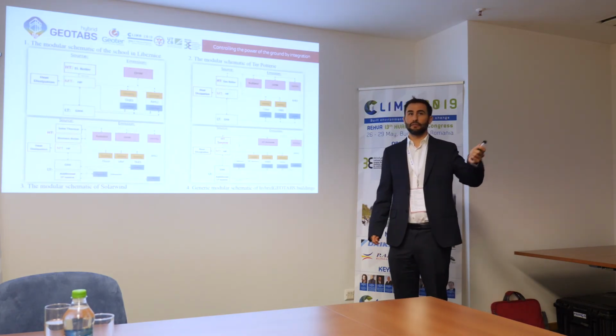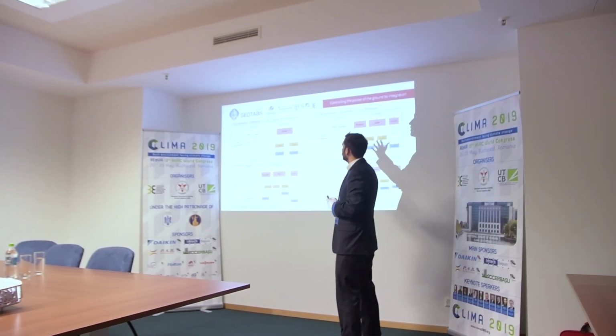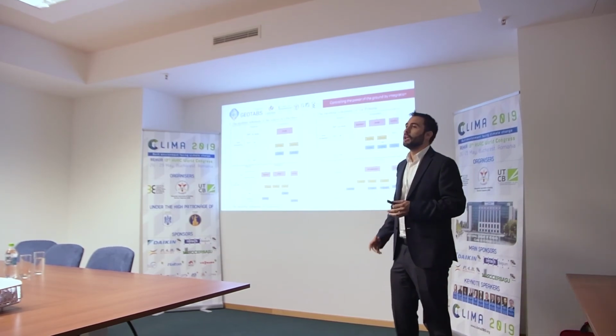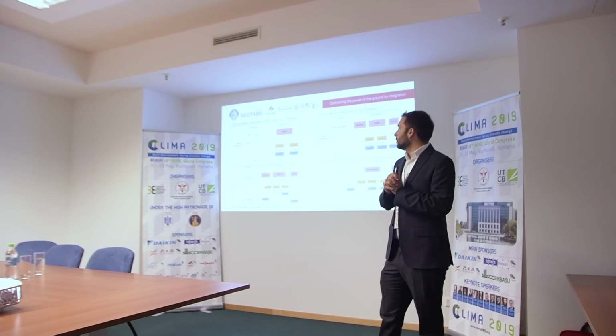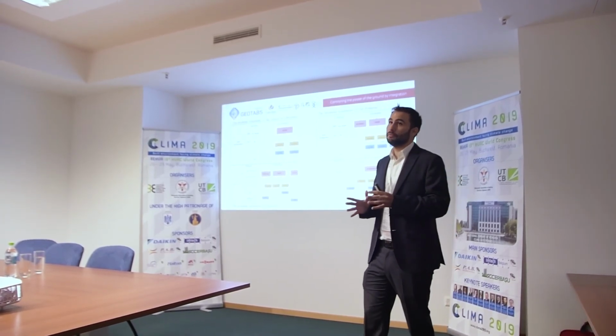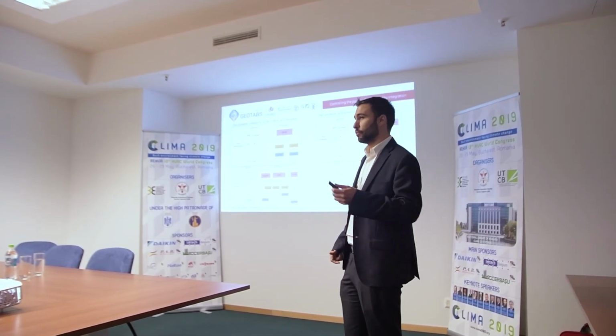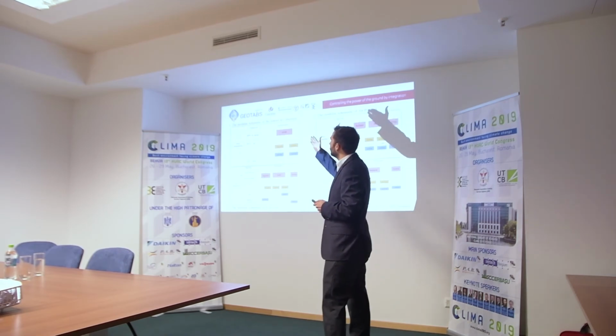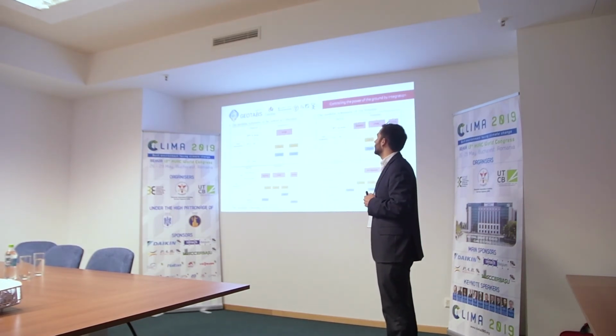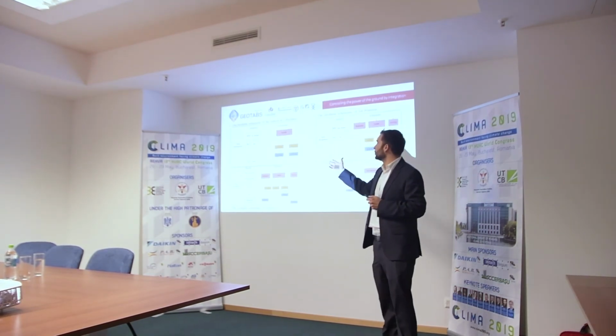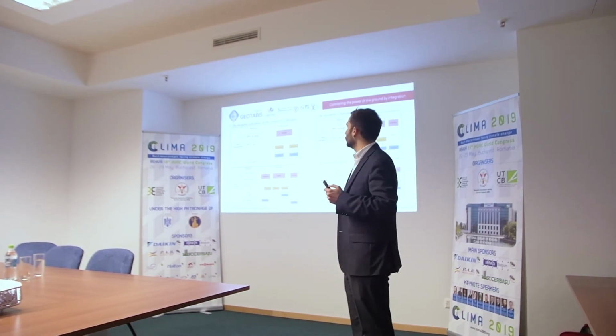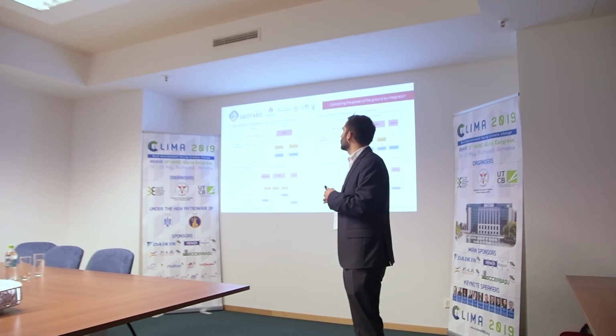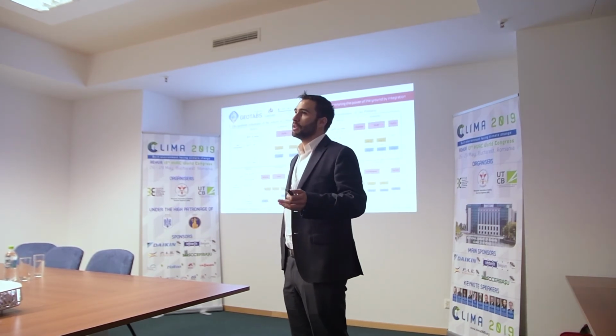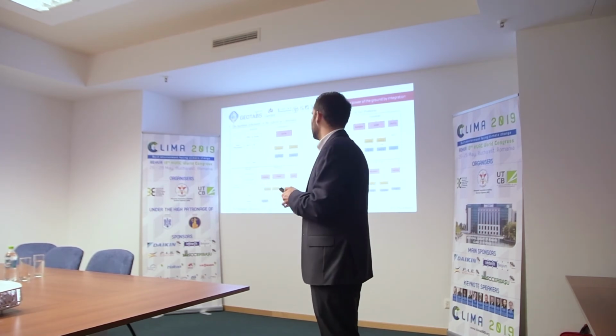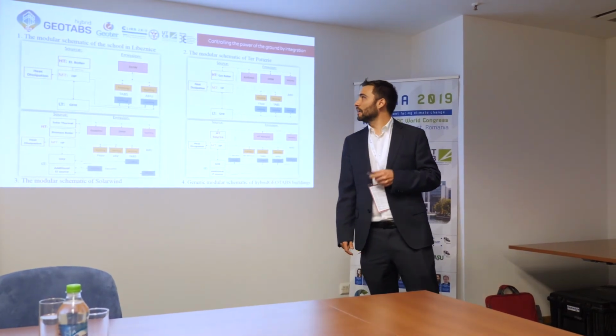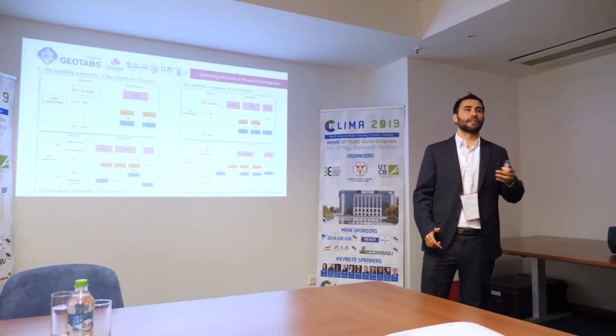So, as Lieve has talked about, this is a modular schematic of different GEOTABS buildings in Europe. The MPC GEOTABS project is focused on medium-big installations, medium-big buildings, more than 1,000 square meters. And in this kind of buildings, we can find different energy sources and different emission systems. So, for example, as low temperature sources, we can find different kinds of ground exchangers. For medium temperature sources, we can usually find heat pumps: water source heat pumps, brine source heat pumps, or air source heat pumps. And for high temperature sources, we normally have gas boilers, thermal panels.